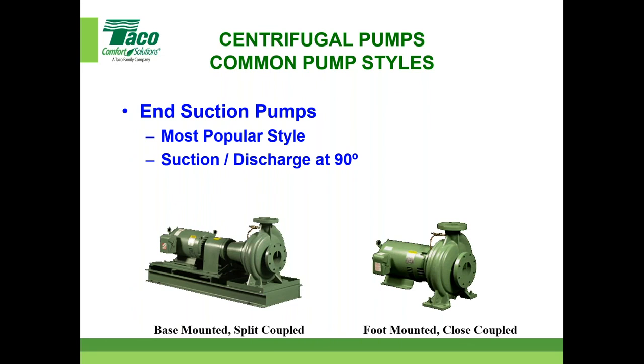We've actually seen pieces of equipment like that. If the pump's installed correctly and that component's installed correctly, that's a great recommendation. But what we've seen is those couplings, some of them are braided. I've actually seen them not straight. I've seen them twisted. So you know that there are forces and the piping's not installed correctly. So like Rich says, it's a difficult answer from a quick standpoint. It doesn't hurt as long as things are installed correctly.